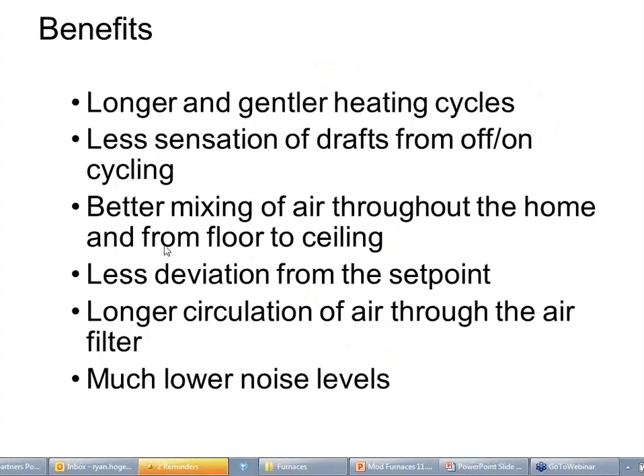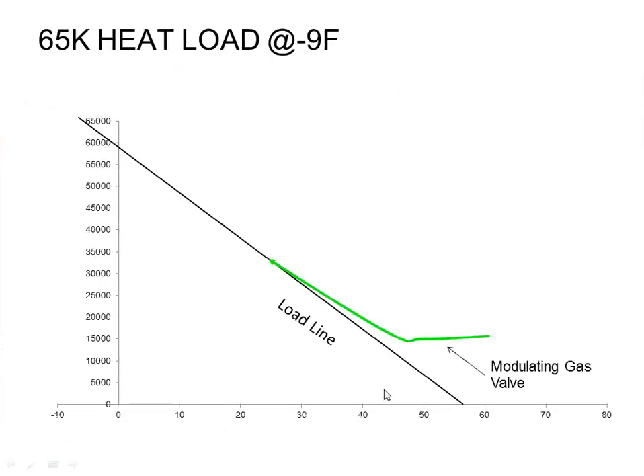In terms of the gas consumption, with homeowners, you need to have this conversation with them in advance and explain to them that this furnace is going to be running nonstop a good chunk of the winter. Right? Now, at some point, let me go back here. At some point in time, I'm not going to be able to modulate as low as I want, right? Because 40% is the minimum. Let's just say on this chart right here, this is the 40% minimum line, right? So I'm going to ramp this gas valve up and down, up and down, and up and down. And at some temperature, and in this particular house, let's say it's 48 degrees outside, at some temperature, I'm not going to be able to ramp it down as far as I want, and I'm going to have to go ahead and shut it off.